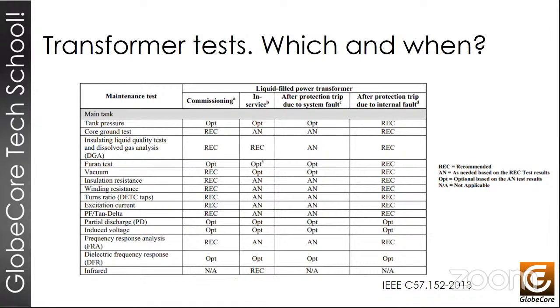We now have different tests, and we see that depending on the scenario, we run the recommended test first, then the test that might be required or as needed, and then the optional test. And that leaves us with the tests that do not apply, which we obviously don't do. For example, when there is a problem in the transformer, when our transformer protection trips, one of the most important recommendations is to run the Furan test. And this will tell us the insulation characteristics of the transformer. But in other cases, this test is still optional.